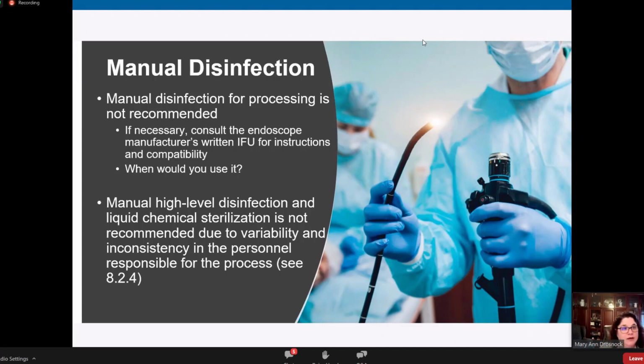We do have that in there for an emergency situation, if your AERs went down and you still have procedures that have to be done. But generally, we want to move the industry to reprocessing scopes in automated systems, in your AERs, because there is so much evidence out there to support that your AERs are going to do a better job, a repeatable process. They're going to flush higher volumes of fluid, your disinfectants and detergents and all of that, through the scope than we could ever do manually with a syringe. So we do want to think about those implications.